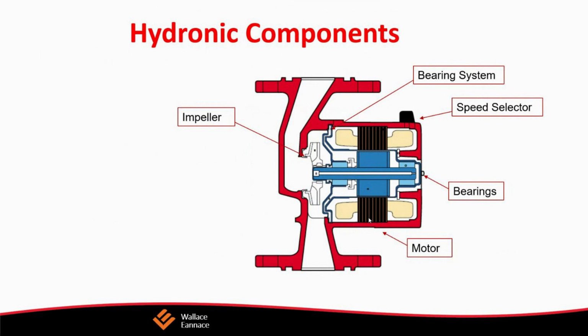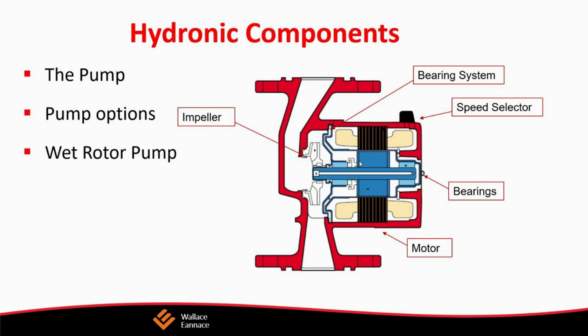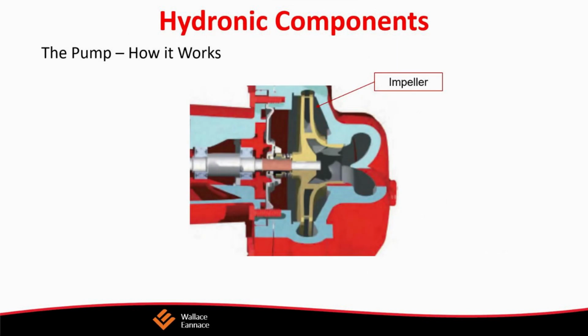So the pump, looking more at how it works: centrifugal pumps, which is what most pumps used in heating applications are, have a spinning impeller that gives velocity to the water. The velocity is captured in the volute, which creates a pressure difference between the inlet and discharge sides of the pump. Centrifugal pumps do not pull or suck water. They're actually a pressure machine. They create a pressure differential. One side is low pressure, the other side is high pressure. And of course, water is always going to want to go from high pressure to low pressure, and that's how we create flow. Simply, water enters into the eye, goes out the perimeter of the impeller, creates a pressure differential, and that's how the water travels. Centrifugally, it exits out the volute.